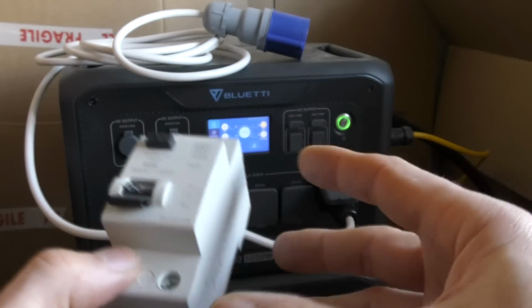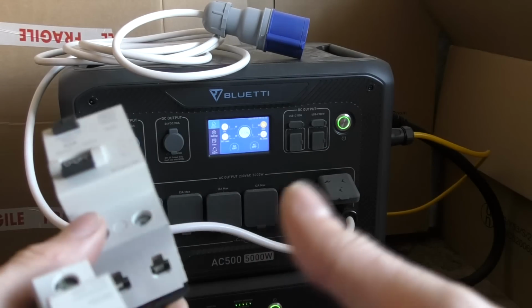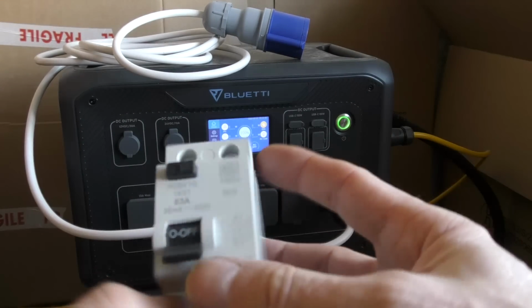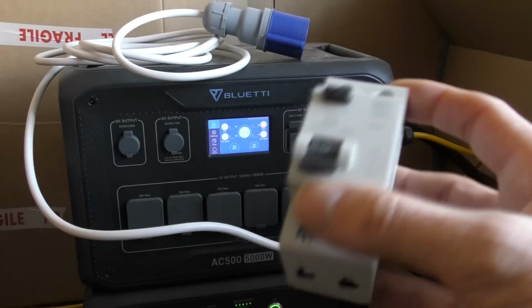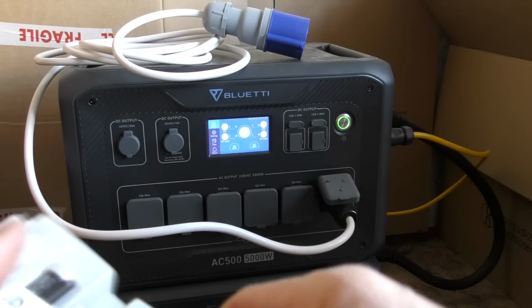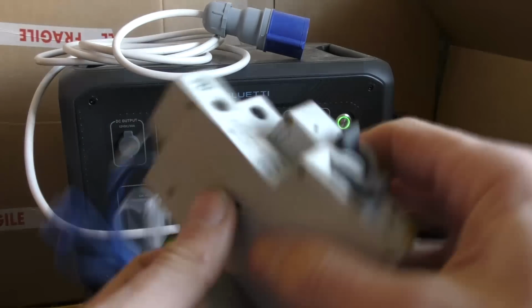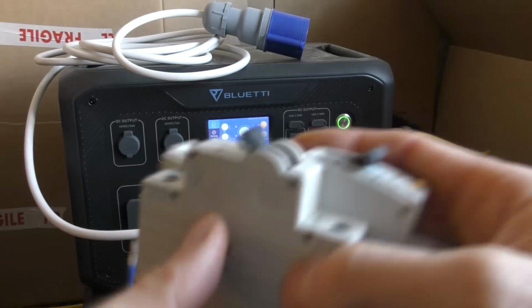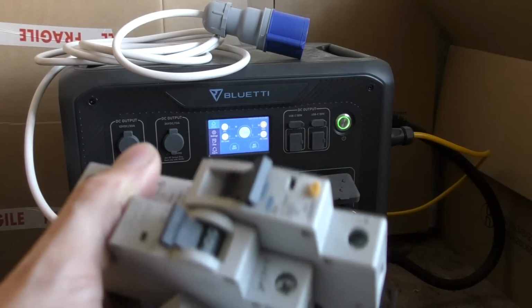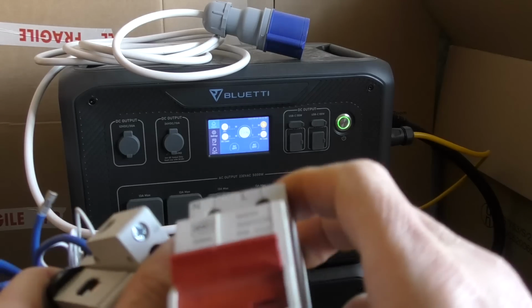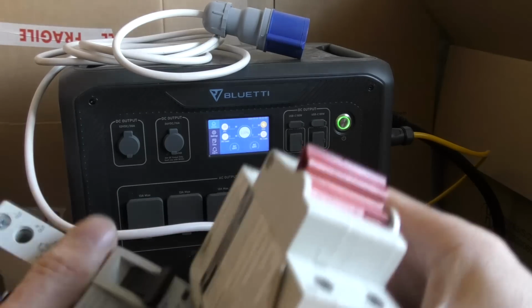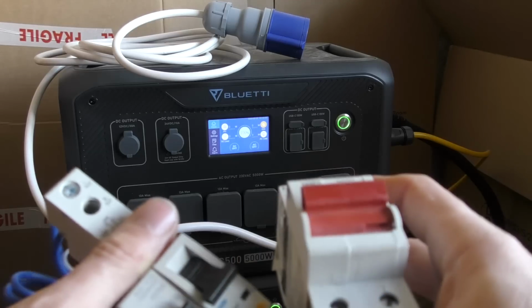If you've got one of the older systems that has two RCDs, one advantage of converting to RCBOs is you actually gain some spare slots. Normally you have two of these, that's taking up 4 slots. Whereas if you just replace all your existing breakers with RCBOs, then that gives you effectively 4 free slots, because all the solutions for doing the switch over use more slots than the standard incoming breaker. So that's a handy way of both improving your installation and gaining some free slots.